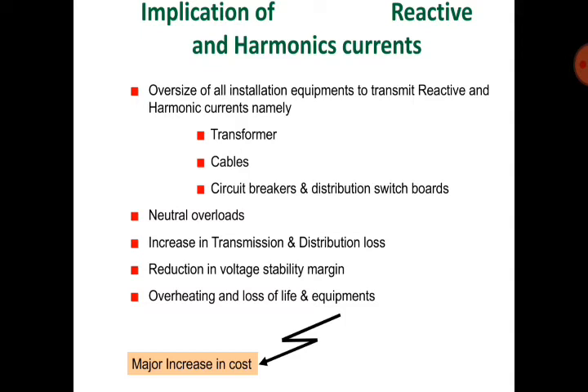Implications of reactive and harmonic currents include: oversizing of all installation equipment to transmit reactive and harmonic currents — namely transformers, cables, circuit breakers, and distribution switchboards — neutral overloads, increase in transmission and distribution losses, reduction in voltage stability margin, overheating and loss of life in equipment. Considering all these things, there is a major increase in cost.